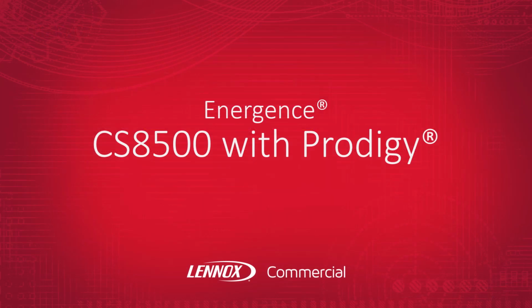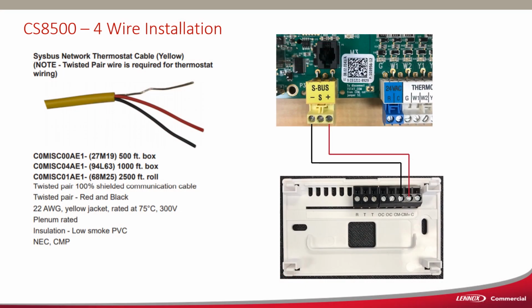We also have what we call our Comfort Sense 8500 thermostat, to be used with any unit that has a Prodigy board. This really is not a thermostat. It's actually a sensor, a programmable sensor with a time and day schedule. If you look to the right, you'll see we're wiring this unit straight to the sysbus terminal on the Prodigy board, just 2 wires. And those wires do need to be shielded, twisted, 2 pair, stranded with a ground.